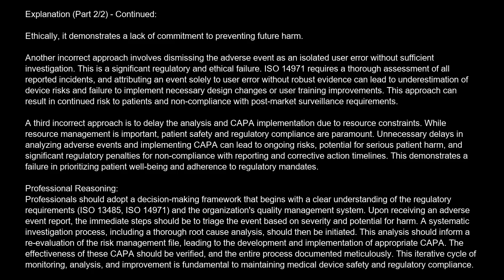Professional reasoning. Professionals should adopt a decision-making framework that begins with a clear understanding of the regulatory requirements, ISO 13485, ISO 14971, and the organization's quality management system. Upon receiving an adverse event report, the immediate step should be to triage the event based on severity and potential for harm. A systematic investigation process, including a thorough root cause analysis, should then be initiated. This analysis should inform a re-evaluation of the risk management file, leading to the development and implementation of appropriate CAPA. The effectiveness of these CAPA should be verified, and the entire process documented meticulously. This iterative cycle of monitoring, analysis, and improvement is fundamental to maintaining medical device safety and regulatory compliance.